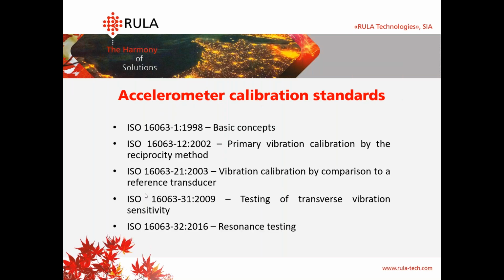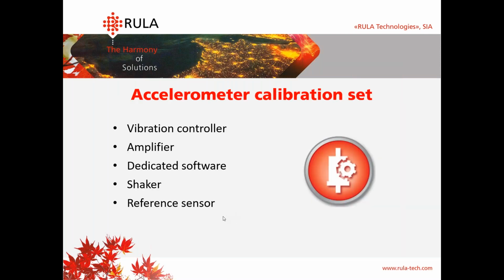In our software, we met all the requirements of the ISO 16063 standard. Here you can see all its parts which we met in our software. And in the last part of our webinar, we will talk about resonance testing in accelerometers, and it is covered by the last standard, which you can see here. And now let's continue with our calibration sets.